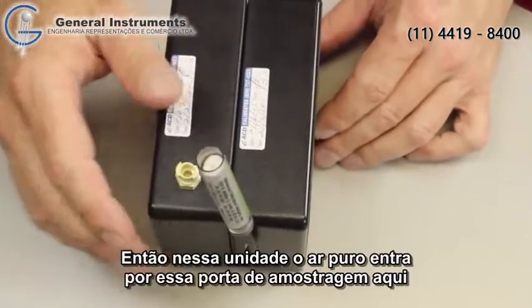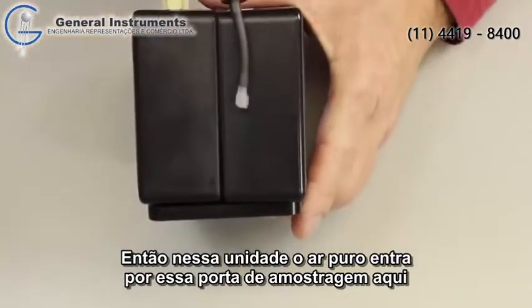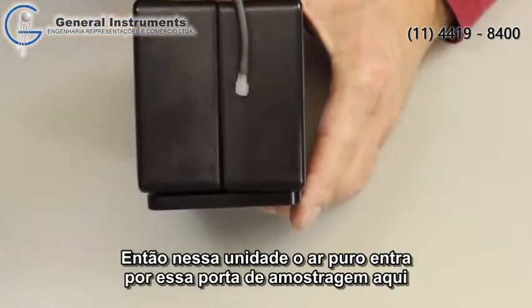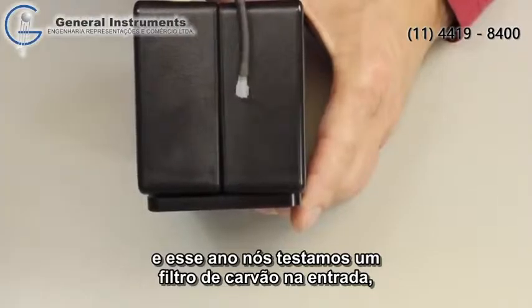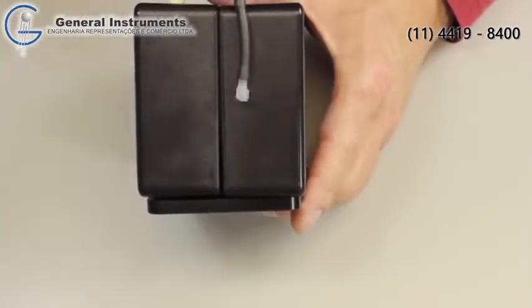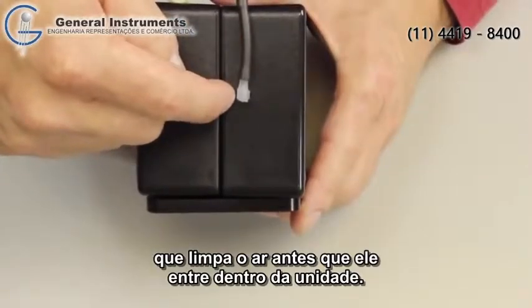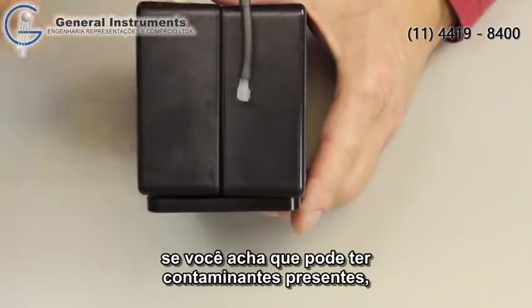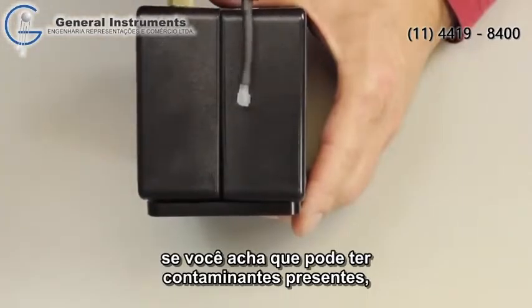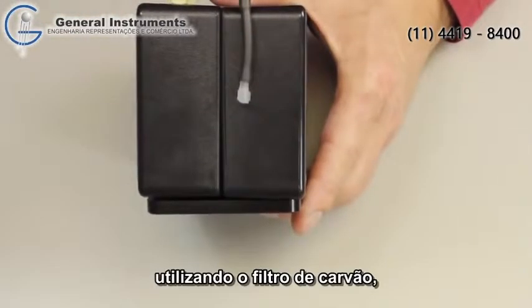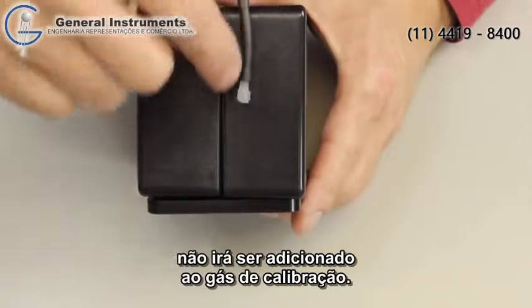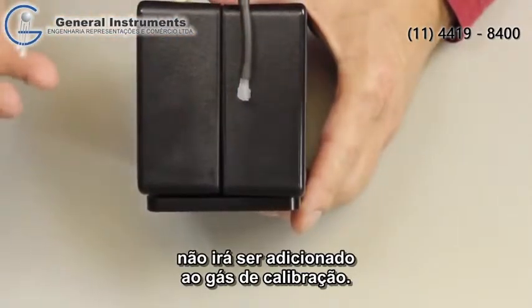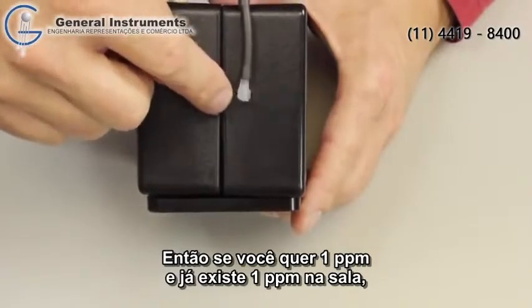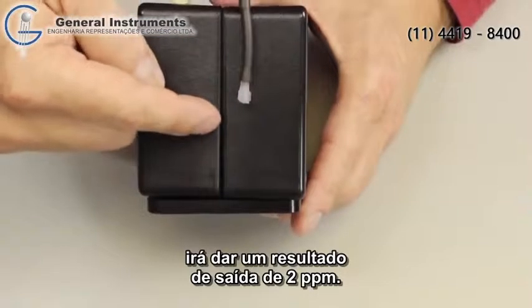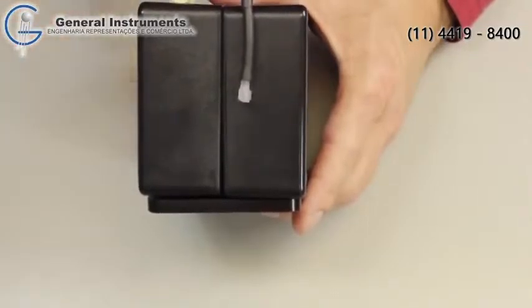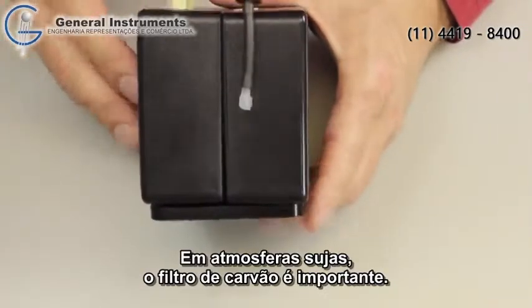All right. So on this unit, the fresh air comes in through this sampling port here. We've got a charcoal filter attached to the unit, so it scrubs the air before it comes into the unit. You need one of these if you think you might have background contaminants. In this case, if you've got ozone in the room, you want one of these charcoal filters in line so that it doesn't add to our calibration gas. So if you wanted 1 ppm and there was already 1 ppm in the room, we would get 2 ppm out. So in dirty atmospheres, the charcoal filter is important.